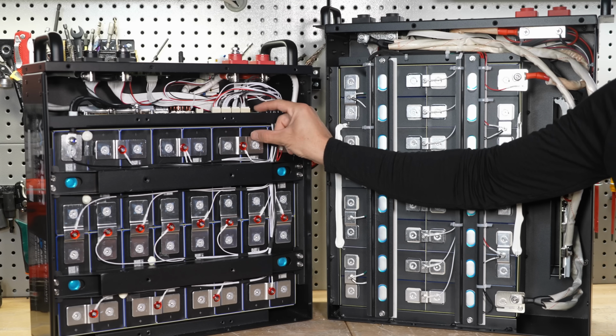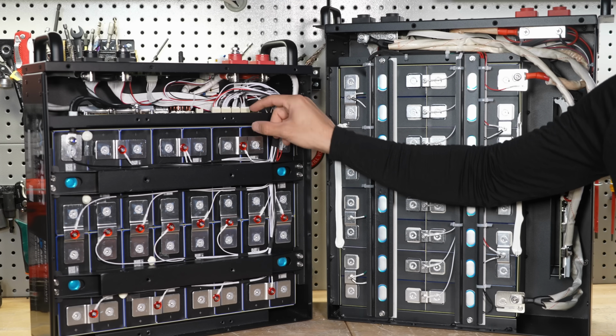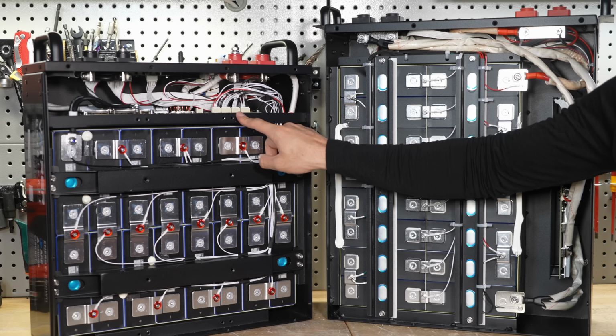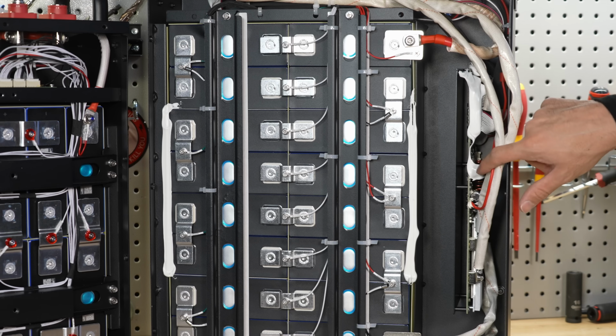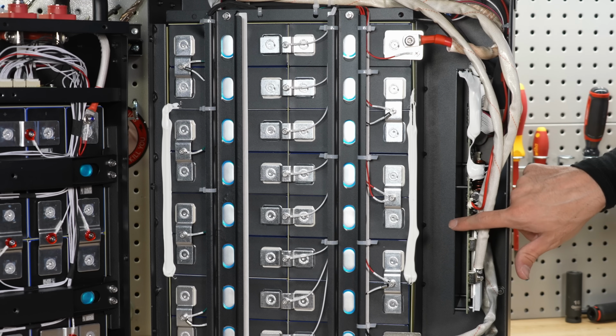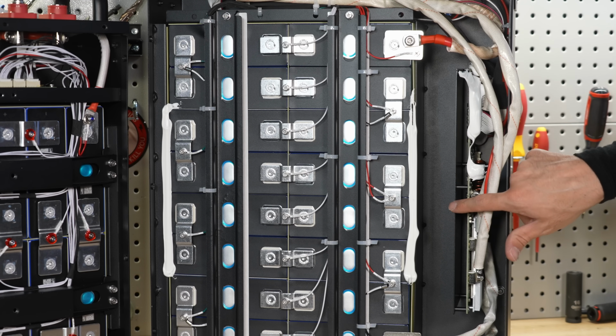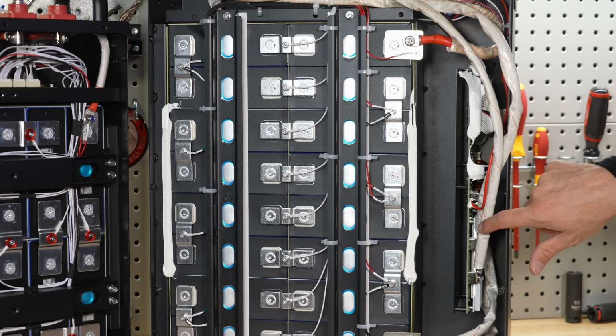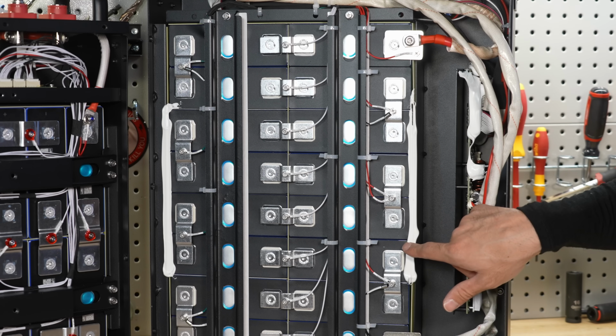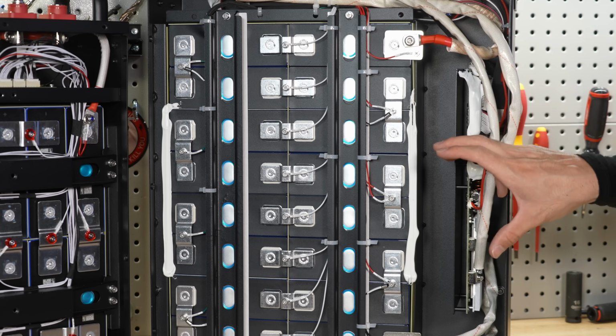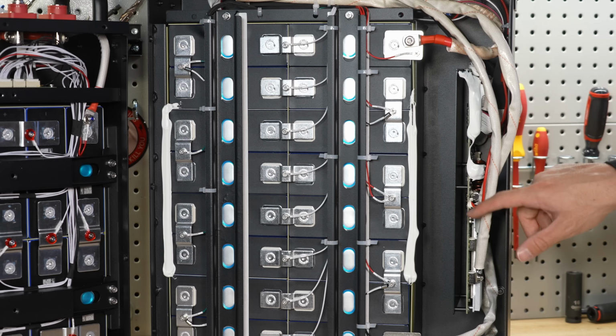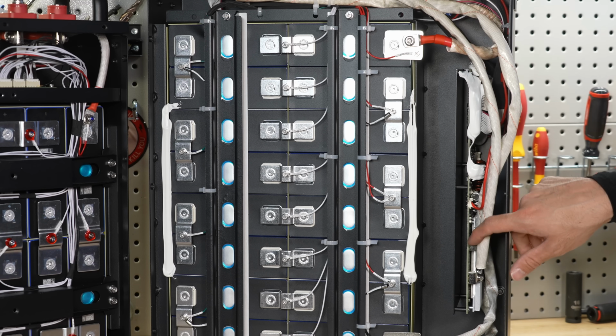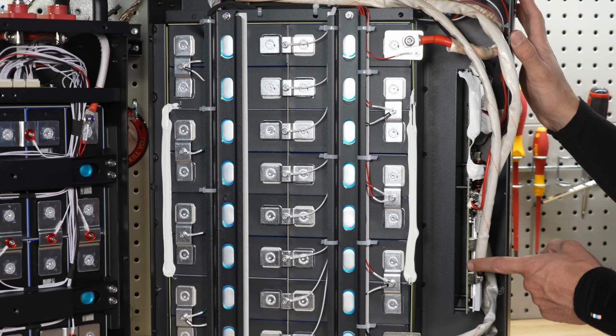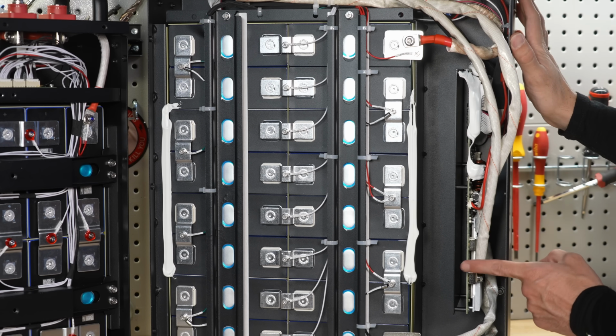The next difference is how close the cells are to the BMS. On the Vatrer, it's pretty close - there's still an air gap and a piece of steel, but compare this to the Ecoworthy. On the Ecoworthy, there's a massive gap, and they put this in a lot of their batteries. I really like this design. If something happens to the BMS, you don't want it close to the cells, or if it gets hot it can make some of the cells warmer over time. This helps the cells age at the same rate. This is the same design they use in their 280 amp hour battery, so yeah, I'm a big fan of this design.